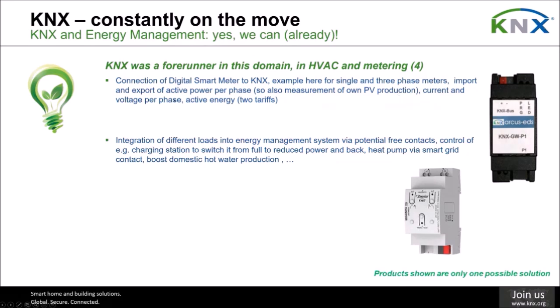Import and export of active power per phase is possible, so also measurement of your own PV production, the current and voltage per phase, the active energy for 2 tariffs. You can connect your digital smart meter and forward this information onto KNX. With simple binary outputs with potential free contacts, you can integrate all different kinds of loads into an energy management system based on KNX.